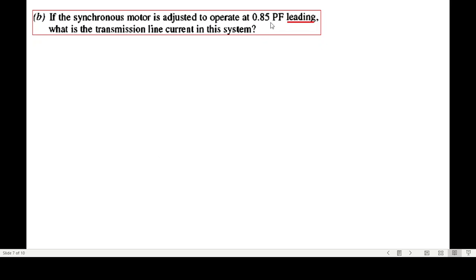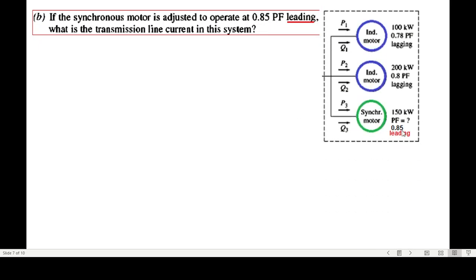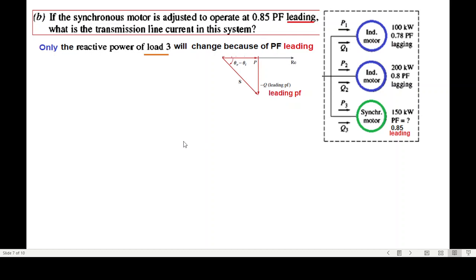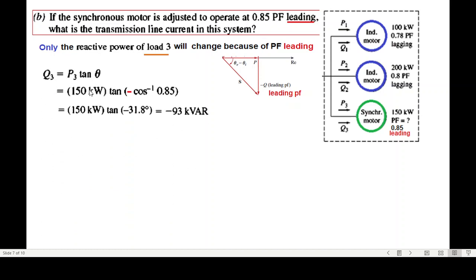For Part 2, the power factor of the synchronous motor (Load 3) is now 0.85 leading. The P and Q values for Loads 1 and 2 remain the same; only Q3 changes. Since it is leading, the power diagram is inverted and Q is negative. Using the formula: Q3 = −P3 · tan(cos⁻¹(0.85)), we get Q3 = −93 kVAR.